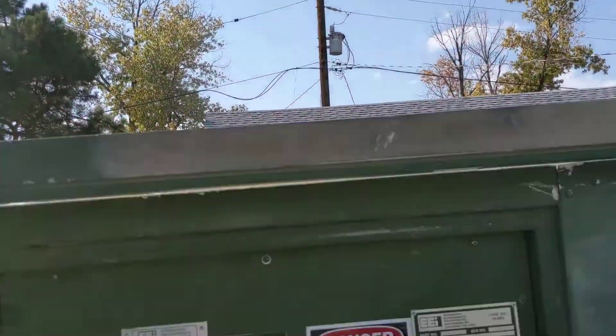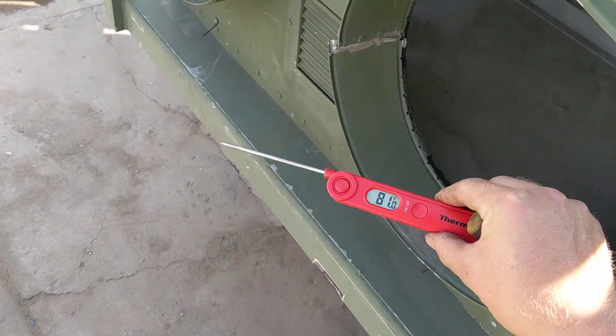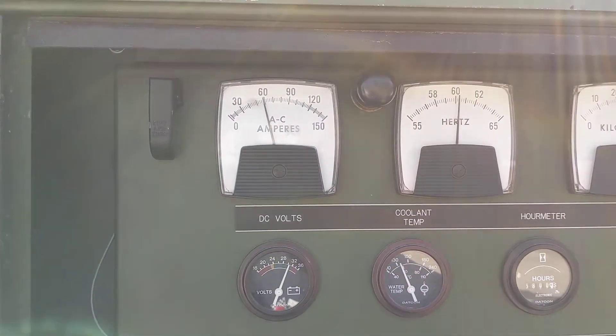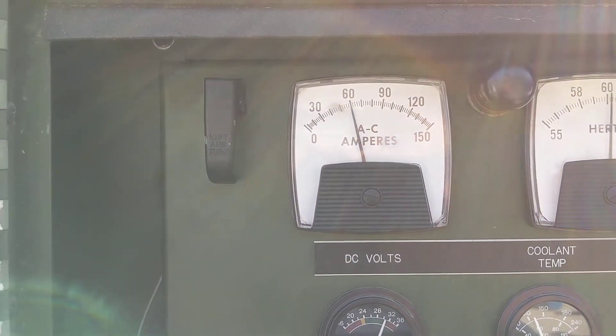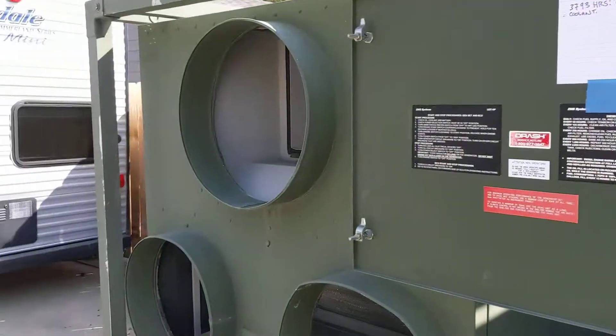You can hear it take load there — compressor turned on. Let's see where our ambient is. About 81, so we'll look at the temperature drop here. That was the condenser fan just kicked on, so we're pulling about 60 amps, just over 20kW with the HVAC on.